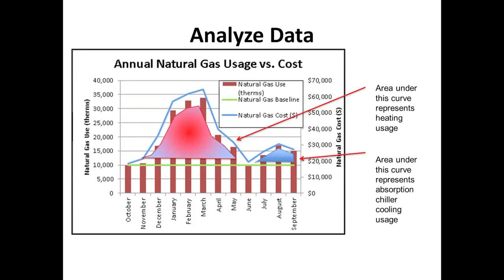Looking at annual natural gas usage versus cost, you'll see that a lot of this natural gas usage was used for heating the building. So where you see that red tie-dyed chart area, that's going to be the area above our baseline for natural gas that was used for heating, because it occurred in the cooler months.